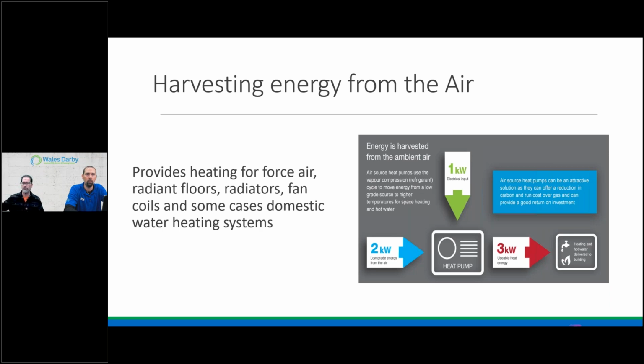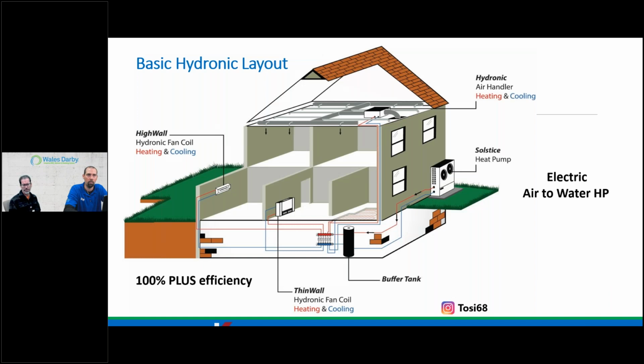Yeah, under compression, moving that outside air across our coil with refrigerants, R410A, R32 soon, all these factors have changed now, but the technology with inverter driving efficiency higher and higher, even as it gets colder out. And this is just talking about the heating side. Again, anything that we talk about, air source heat pump or air to water, is both summer and winter loads, okay? With a little bit more involved. We need to know our loads to make sure we don't oversize one more for the other season. All right, so harvesting Mother Nature is free energy, which is a bonus.